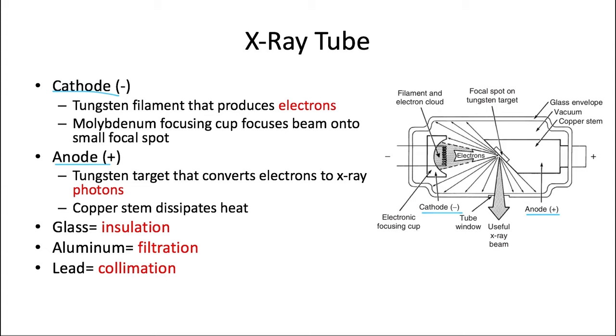So the cathode consists of the tungsten filament that produces the electrons, and so the filament is heated up by the circuitry and electrons literally boil off by thermionic emission. There's also a molybdenum focusing cup, which helps to focus electrons onto the target into a small focal spot.